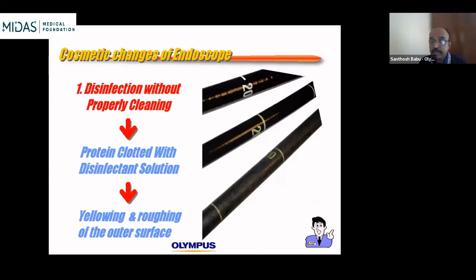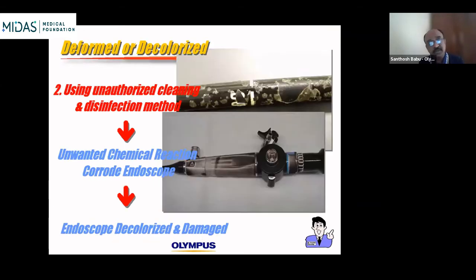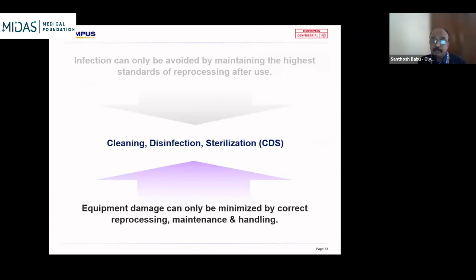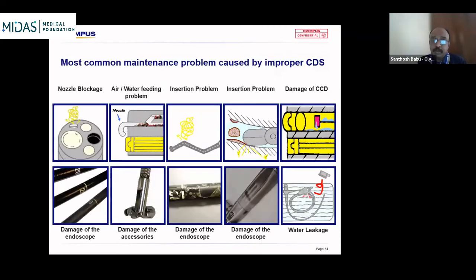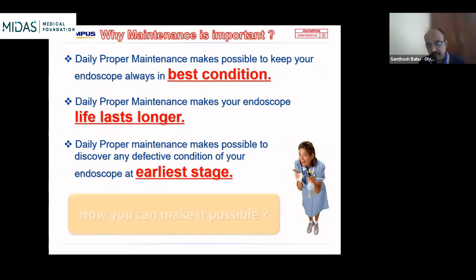If you do not clean the scope properly with the detergent, something called protein fixation happens, purely because of improper cleaning. The color of the scope changes, and cosmetic changes keep happening. Improper disinfectant or detergent use will ruin the scope. So periodic maintenance and regular, daily upkeep of the instrument is very necessary. With daily maintenance, the scope eventually lasts longer.